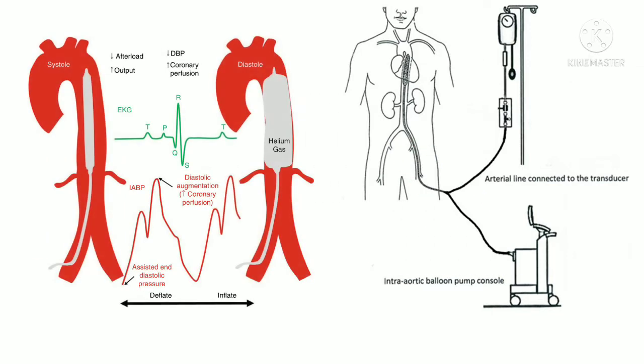This computer console has a mechanism of inflating and deflating the balloon at the proper time when the heart beats. The balloon catheter is inserted into the aorta through the femoral artery up to the descending aorta, and the lower end of the balloon is capped just above the renal artery.